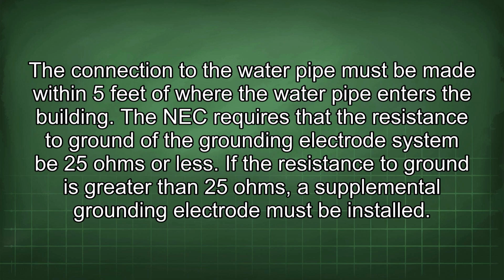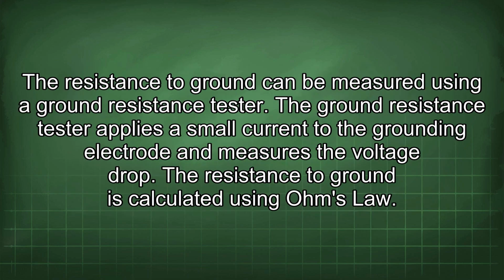The NEC requires that the resistance to ground of the grounding electrode system be 25 ohms or less. If the resistance to ground is greater than 25 ohms, a supplemental grounding electrode must be installed. The resistance to ground can be measured using a ground resistance tester. The ground resistance tester applies a small current to the grounding electrode and measures the voltage drop. The resistance to ground is calculated using Ohm's law.